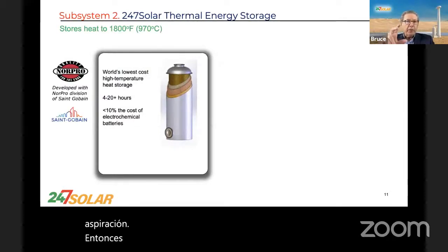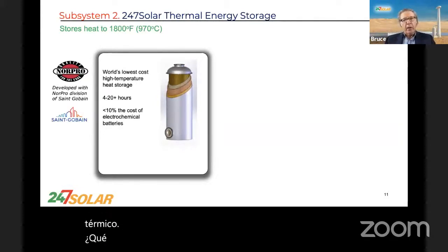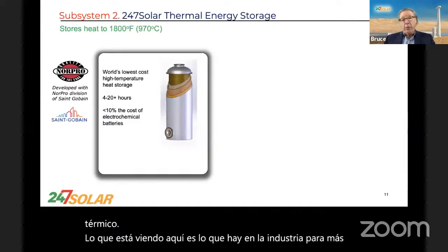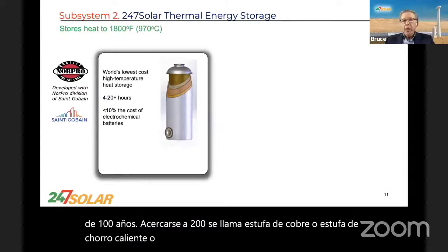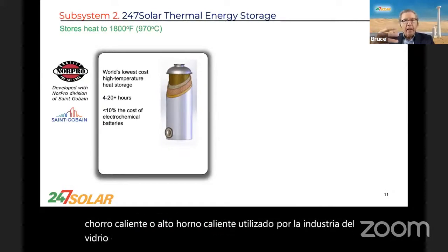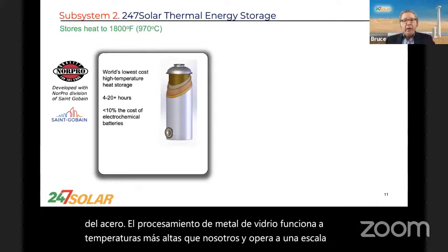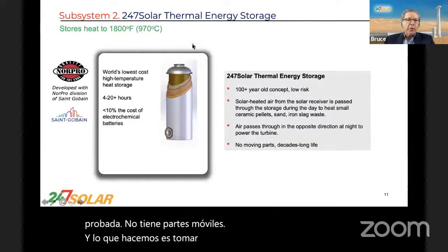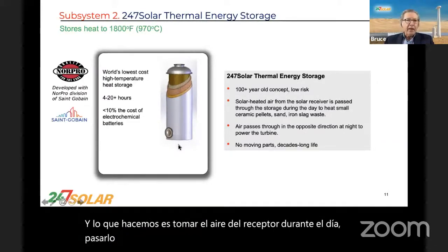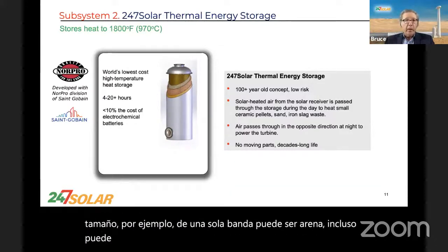The second primary system of our 24-7 solar plant is thermal storage. What we're looking at is what the industry has called, for over 100 years approaching 200, a Cowper stove or hot blast stove or hot glass furnace — used by the steel, glass, and metal processing industries, operating at higher temperatures than we do and at much larger scale. We've essentially shrunk a very proven technology. It has no moving parts. During the day, we take air from the receiver, pass it through the storage media — small ceramic pellets, sand, or even iron slag waste. Very versatile.